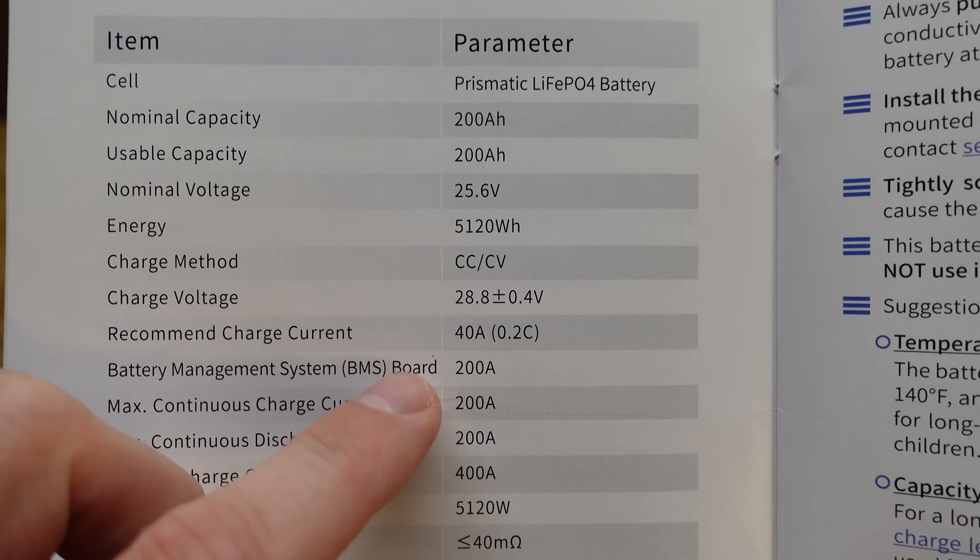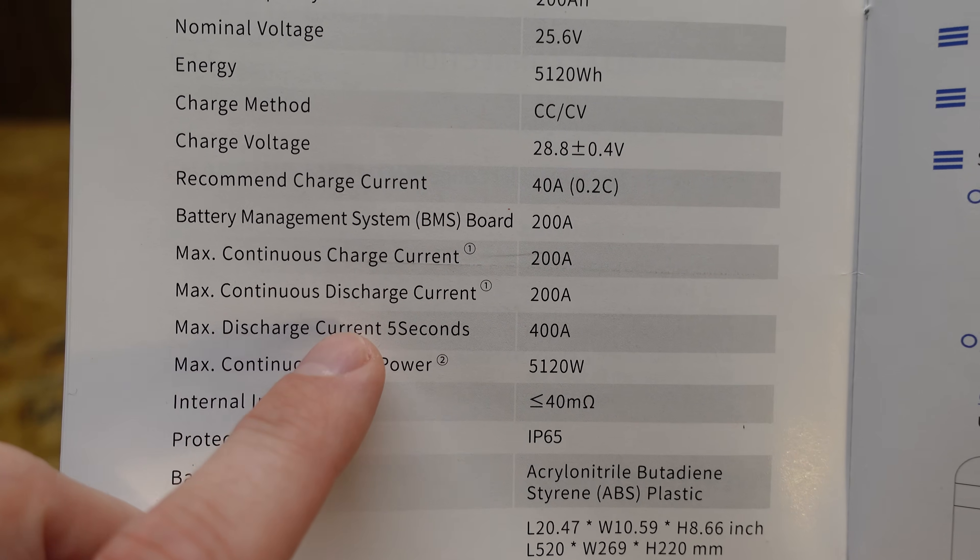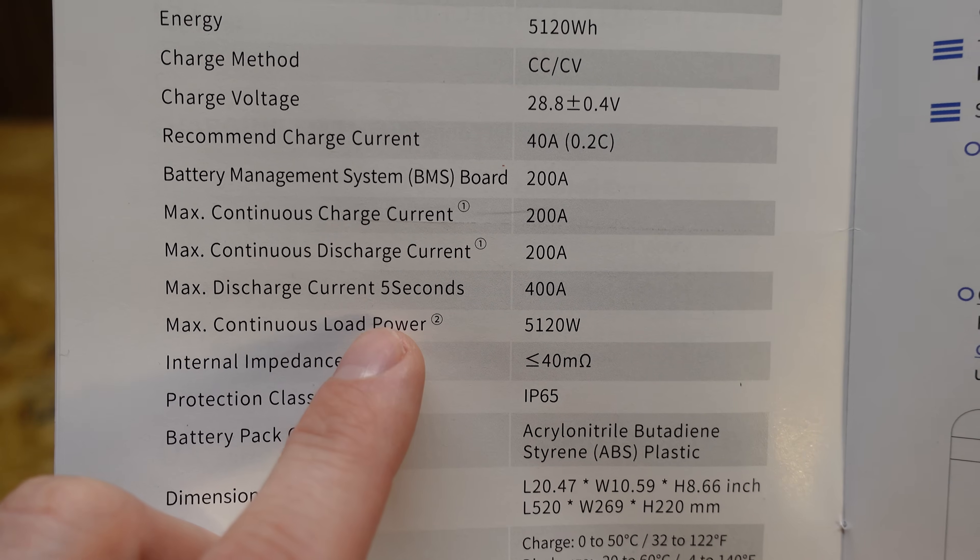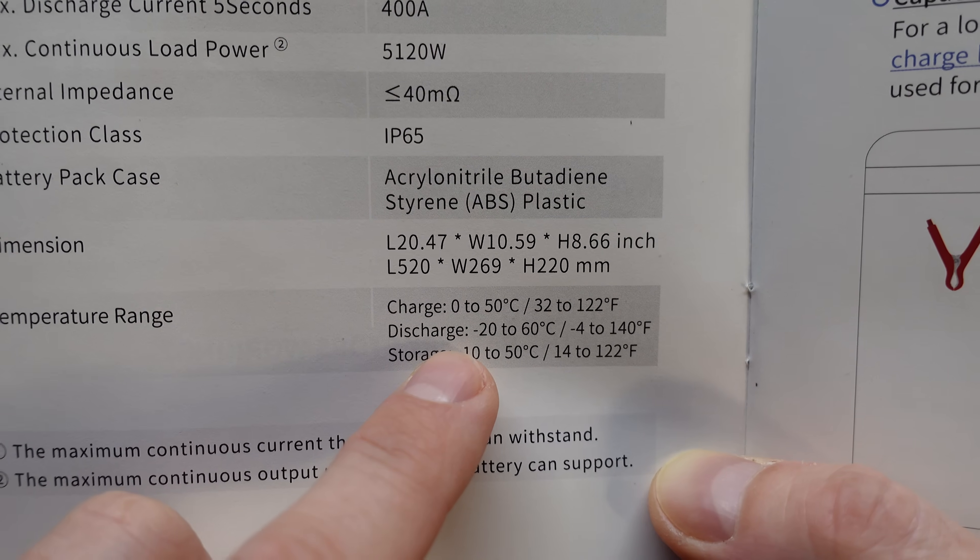So here are the battery specifications. 200 amp hours. Recommended charge is 40 amps. The maximum continuous charge and discharge is 200 amps. Max discharge is 400 amps for up to 5 seconds, so that's your peak rating. And you can charge it down to 0 degrees Celsius.